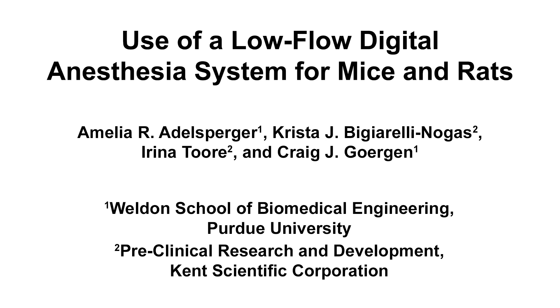This protocol demonstrates the use of a syringe-driven direct-injection vaporizer as part of a digital low-flow anesthesia system. The direct-injection vaporizer accurately delivers anesthesia at very low flow rates compared to a traditional vaporizer, making it a promising alternative for controlled anesthetic delivery to rodents.